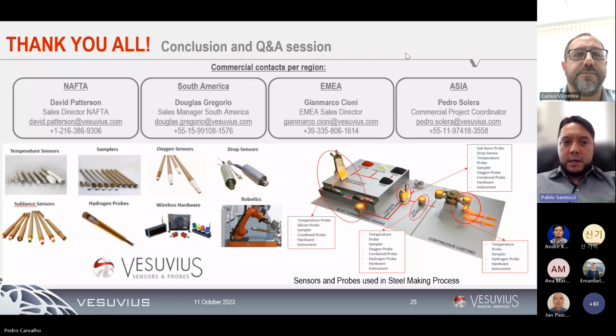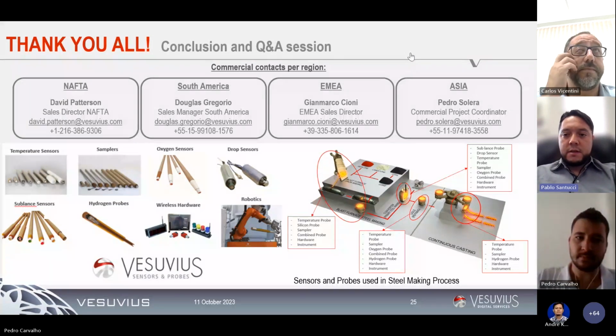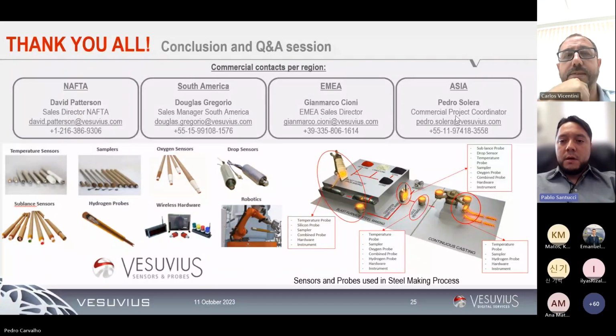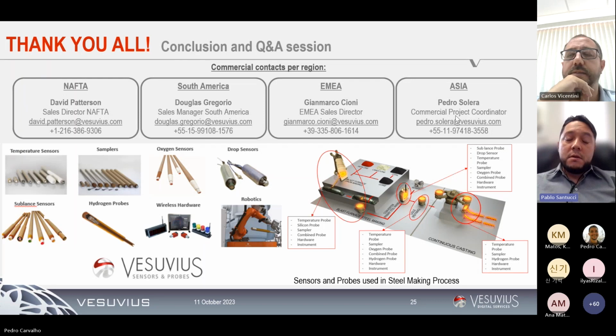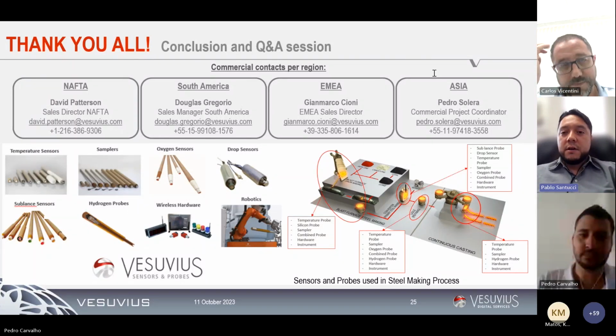Yeah, and just to add some more comments over that question, the minimum purity recommended from the Vesuvius side is 99.97% dry and clean source of nitrogen. So by the time the customer can guarantee that their nitrogen line installation is good to go under those requirements, I don't see any major risk, but bottles are always more, I would say, guaranteed in that regard because it's a sealed container, and certified.